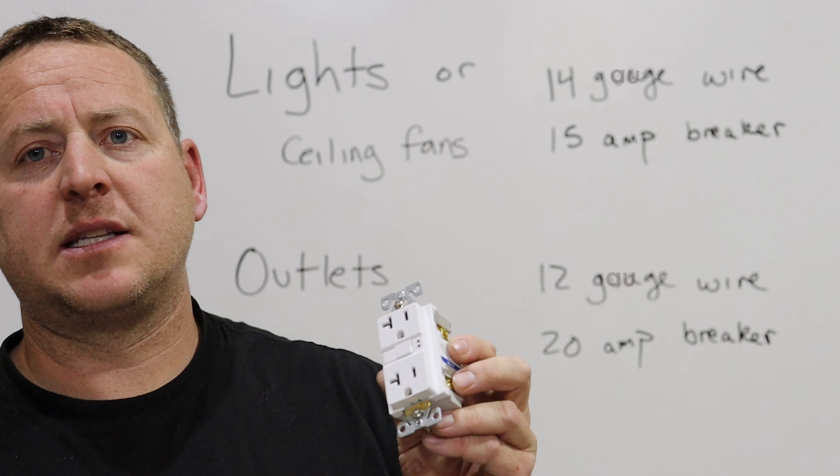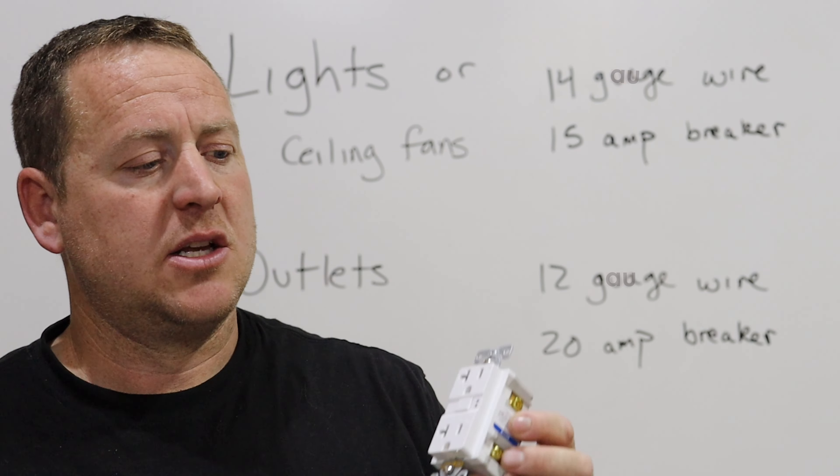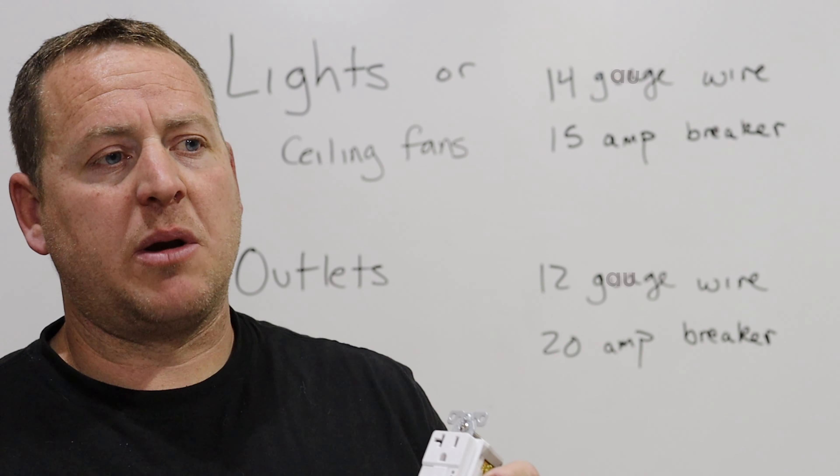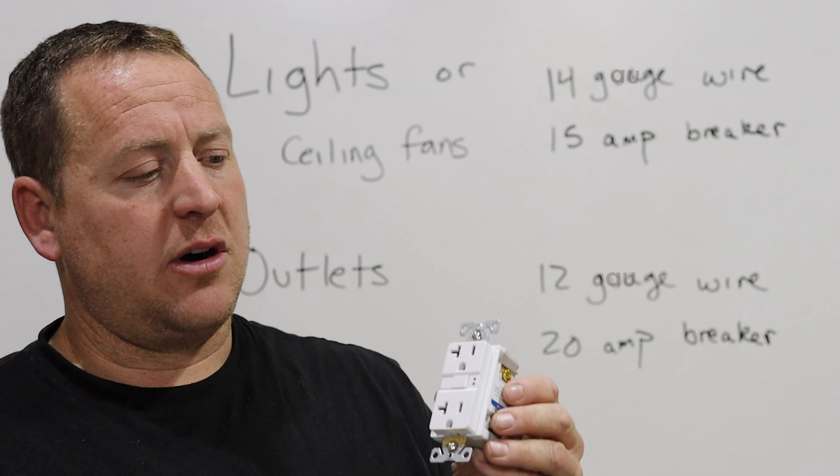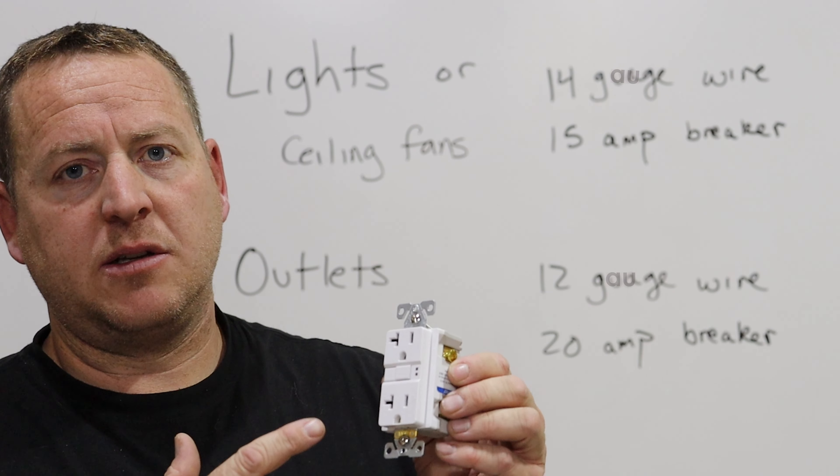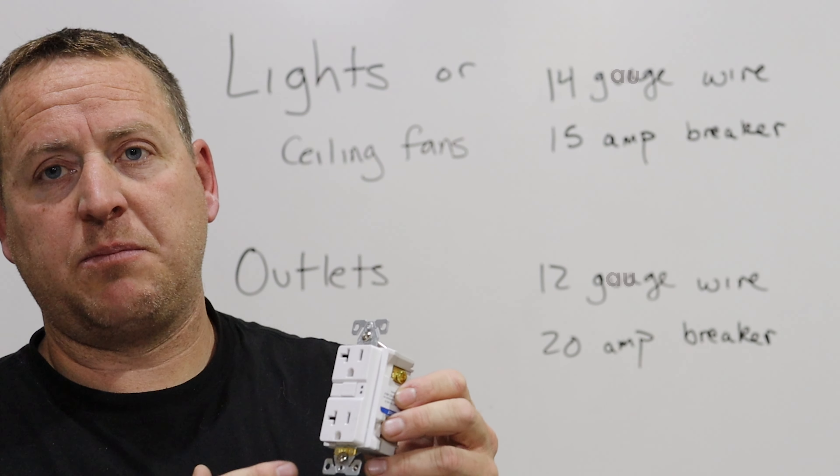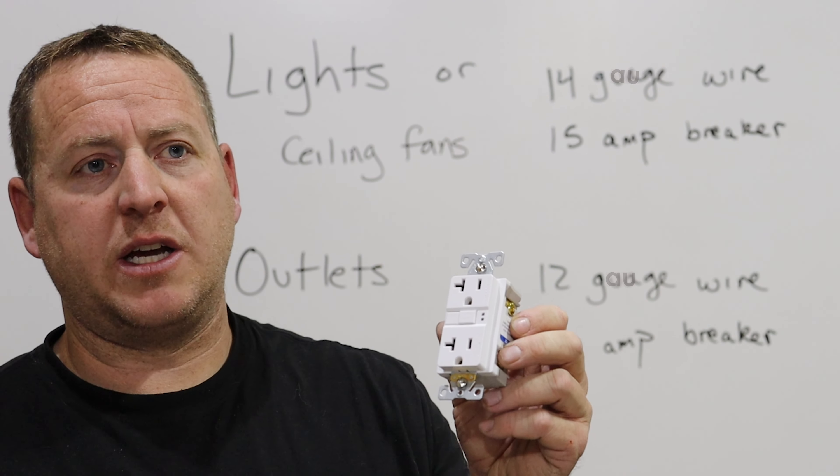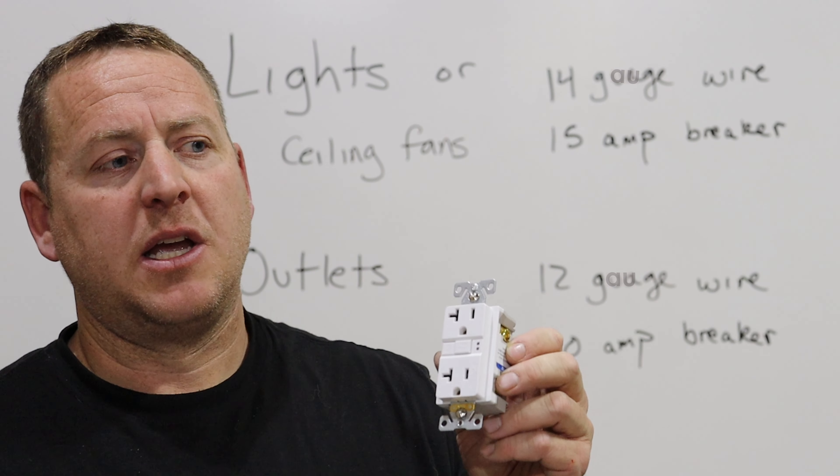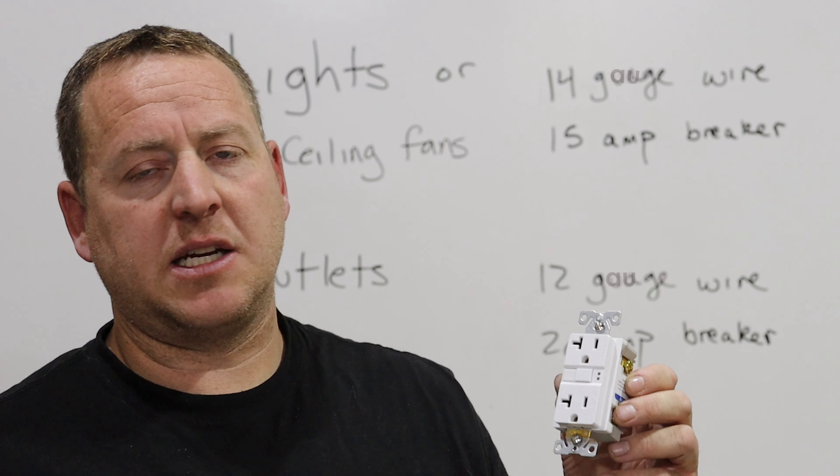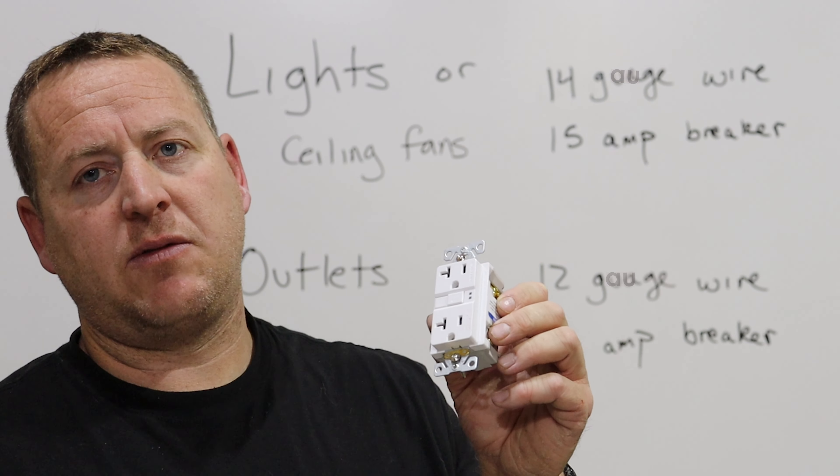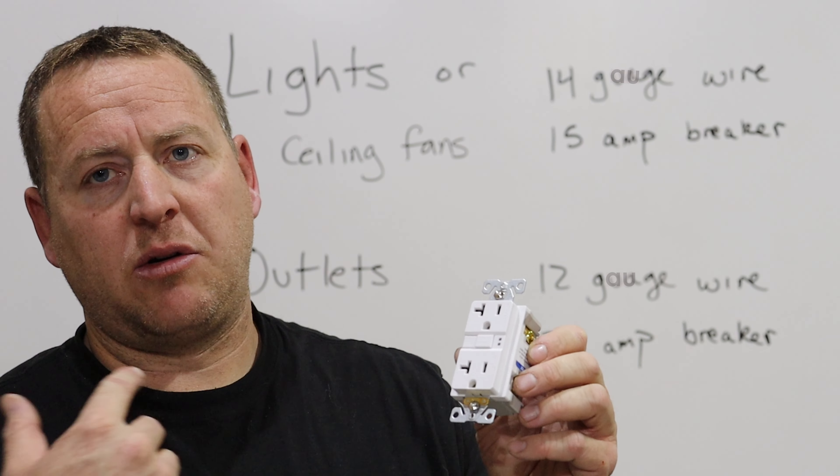They do make some outlets rated for 15 amp—you don't want to use those on this circuit. You want to make sure that whatever device you have matches your breaker. If you have a 15 amp outlet or switch, you want to make sure your breaker is also 15 amp. If even one device in a circuit is only 15 amp, you'd want to use a 15 amp breaker to power the circuit.